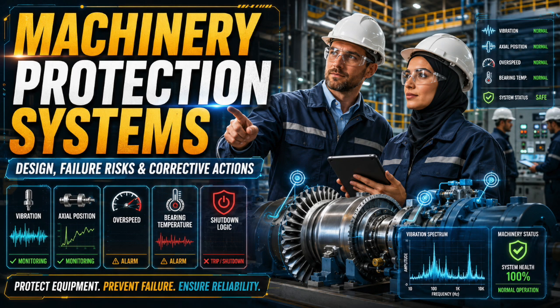Now think about axial position monitoring. This is not a casual measurement. Axial movement can quickly become thrust-bearing distress. When a rotor moves toward active or inactive thrust limits, the machine is telling you that thrust balance, load, internal condition, or bearing integrity may be at risk. If your axial probes are observing the wrong surface, you may not be measuring real shaft axial position. If the target is loose, non-integral, or mechanically questionable, the reading can become misleading. If the active thrust direction is misunderstood, the interpretation can be wrong. If the probe is not correctly zeroed during thrust float setup, the alarm and shutdown points may look correct on paper but behave incorrectly in service.